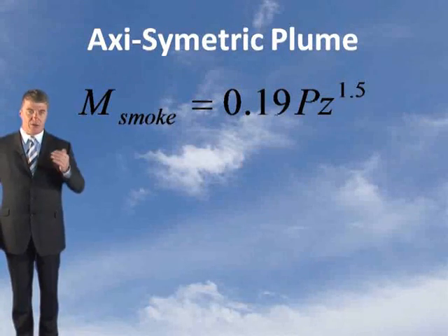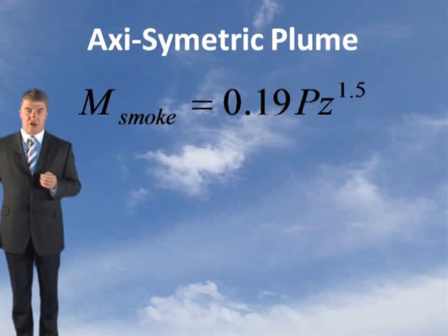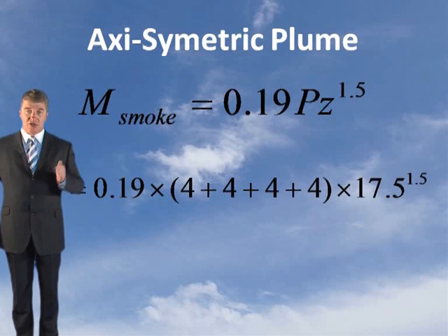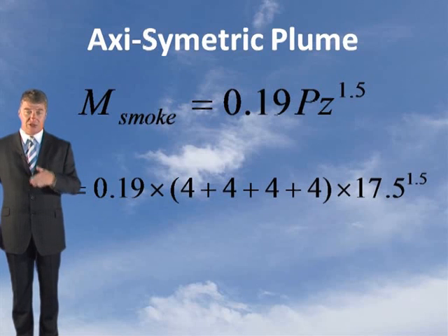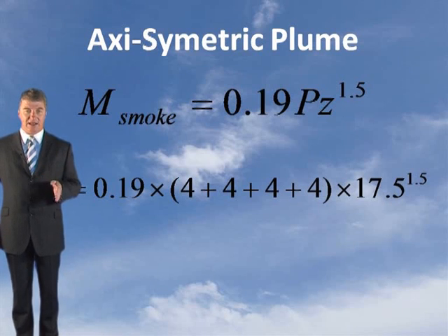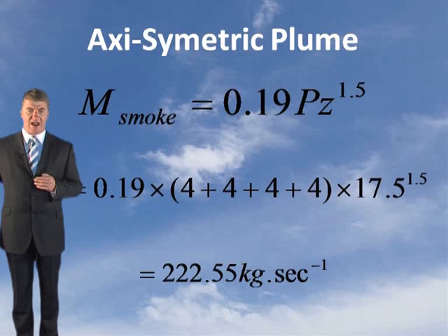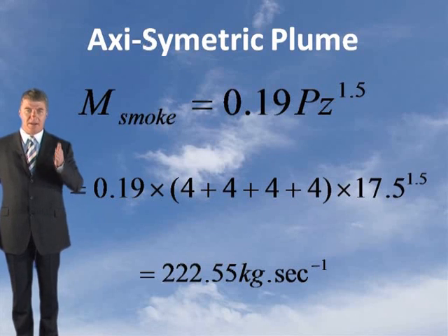Substituting into the formula: M_smoke equals 0.19 times the perimeter (4 + 4 + 4 + 4 = 16 metres) times 17.5 to the power of 1.5. This gives 222.55 kilograms per second, which is the mass flow rate.